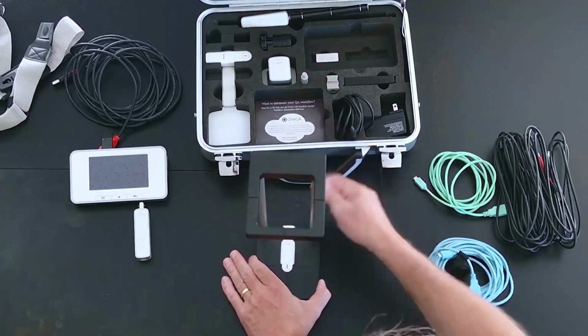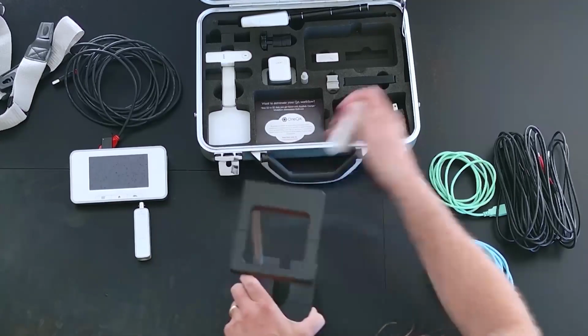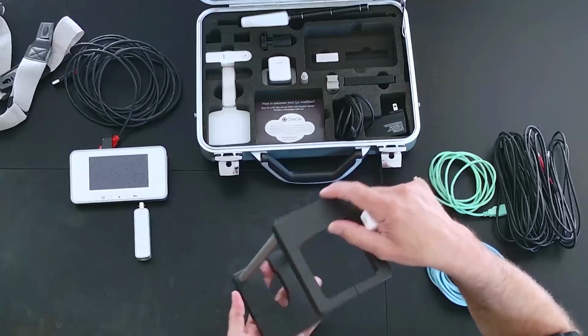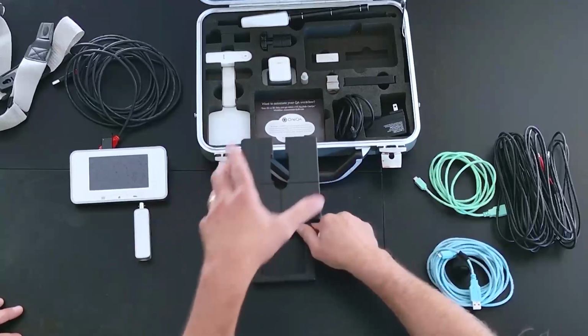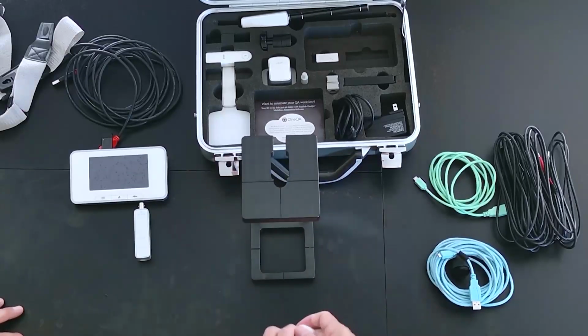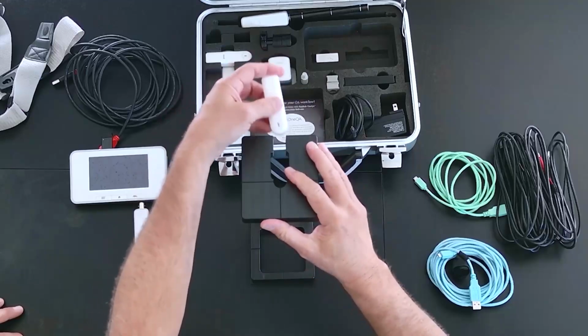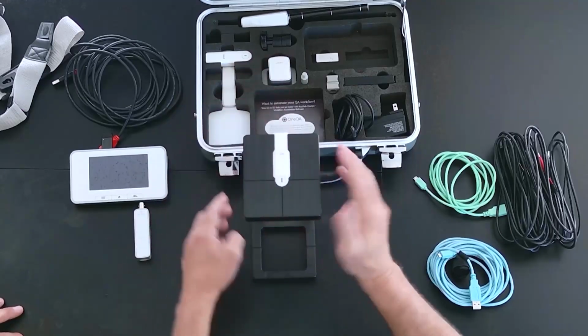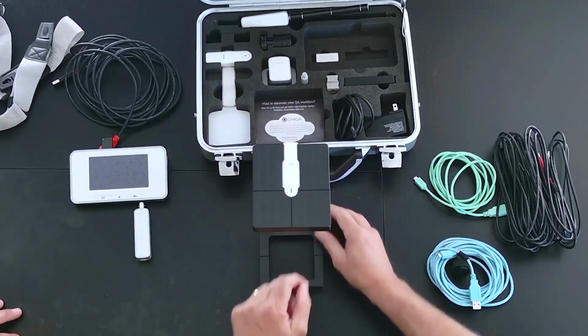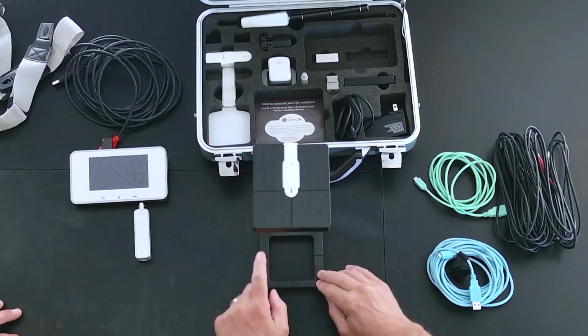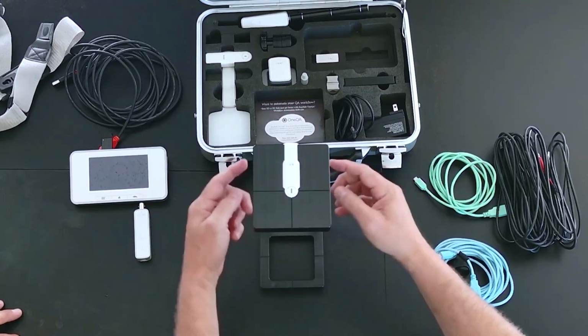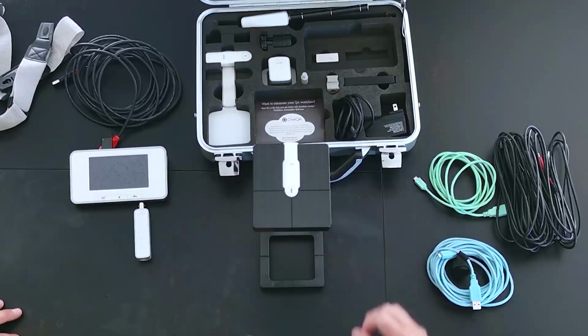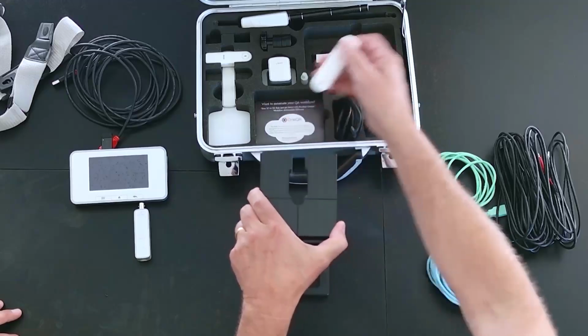So then why do you need a stand? Well, because it's 30 centimeters. How many inches is that? About 12 inches. Right, 12 inches. So 30 centimeters high. Many times you need to measure the dose rate on a fluoro system 30 centimeters off the image detector. And this places the sensor at exactly 30 centimeters above the image detector. So there you go. So you can do that with it. Yes, you can. What else?